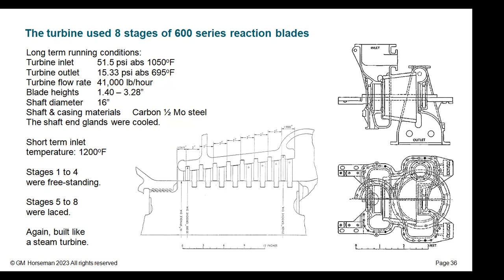Of course, that was 1950. The material didn't exist when this was built. Carbon half moly was the best that was available when you didn't have austenitic steels you were permitted to use. So it's really a material for 900 Fahrenheit, and it was being used here at 1050 to 1200 Fahrenheit application, and that limited the running hours.